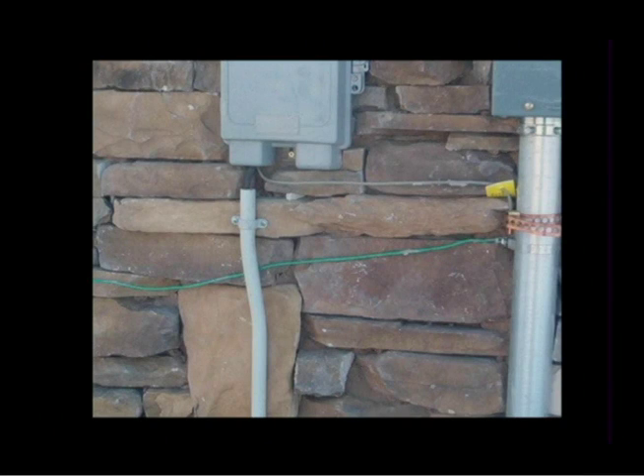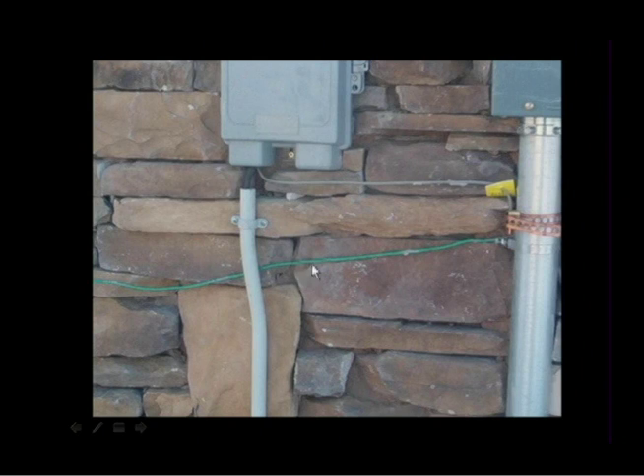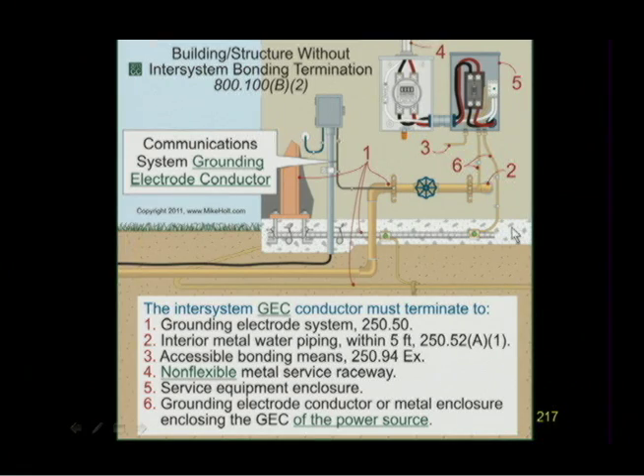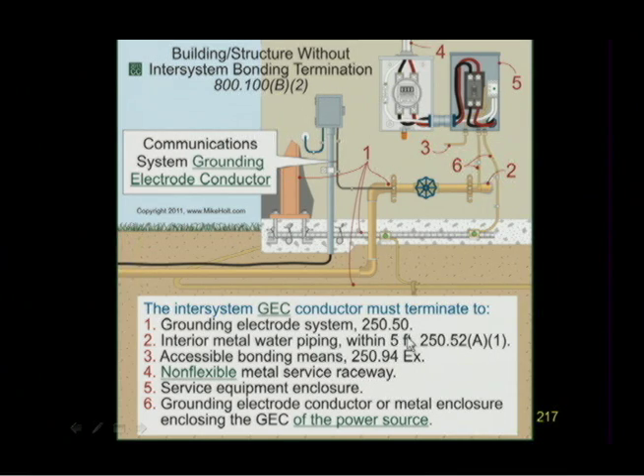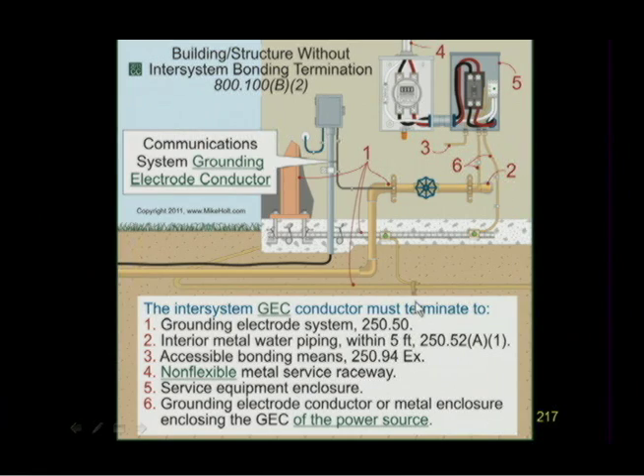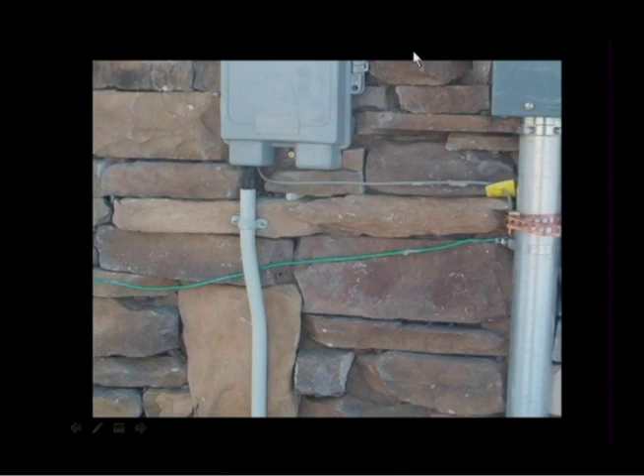Here's an example photo — no inter-system bonding terminal, existing installation. You simply run over to the building service raceway. Options include: the grounding electrode system, interior metal water piping within five feet of entry, accessible bonding means, or non-flexible metal service raceway. That graphic shows option number four — the service raceway. That's one way to do it.